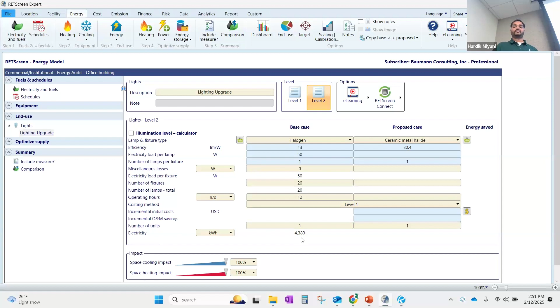So in our base case, we have a halogen lamp, and again, the electricity load per lamp is given as 50 watts per lamp. They haven't mentioned anything about miscellaneous losses, so I will assume it is 0. The number of fixtures mentioned is 20 halogen lamps, operating 12 hours per day. This gives us the electricity consumed by the halogen lamps operating 12 hours per day, which is 4,380 kilowatt hours annually.